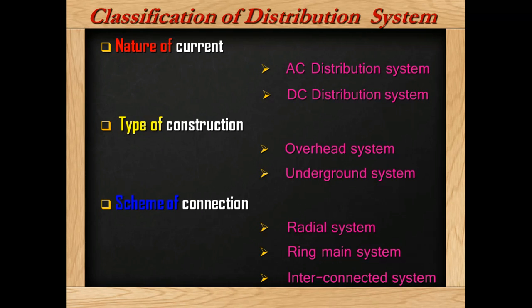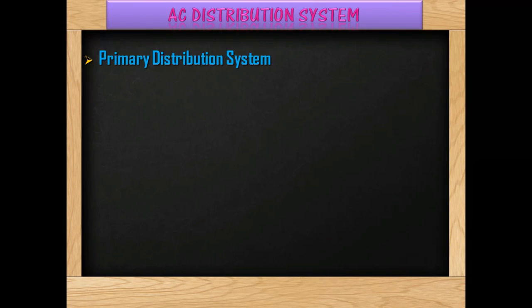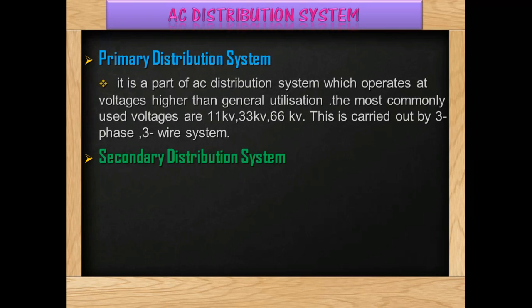Let us discuss about AC distribution system. Primary distribution system and secondary distribution system are the two parts in the AC distribution system. The primary distribution system is a part of AC distribution system which operates at voltage higher than general utilization. The most commonly used voltages are 11 kV, 33 kV, and 66 kV. This is carried out by 3-phase 3-wire.